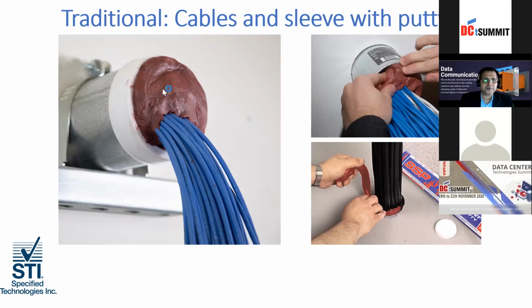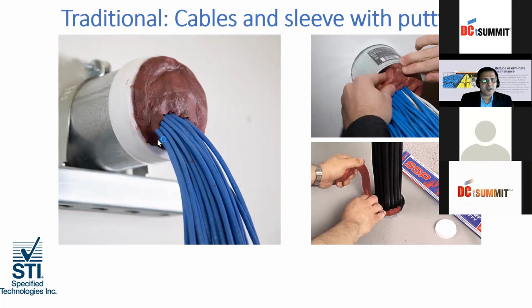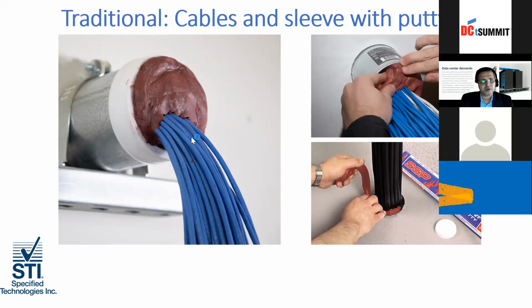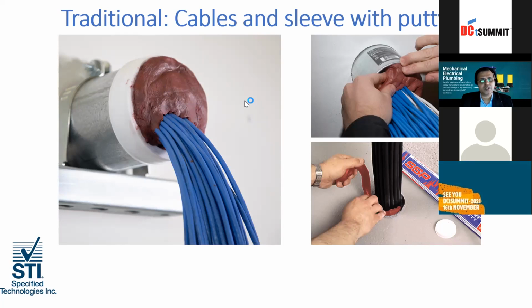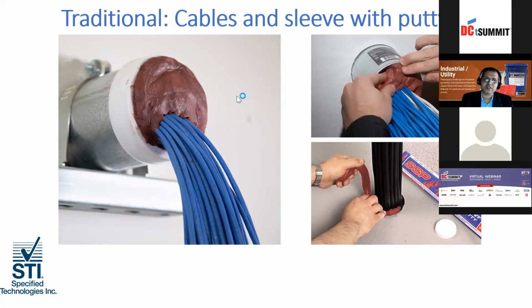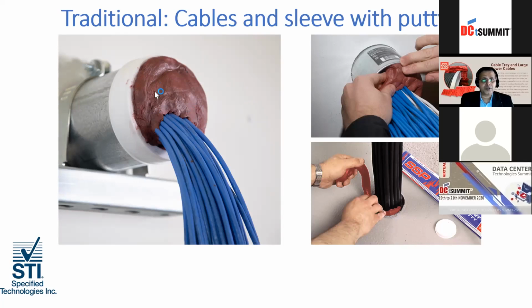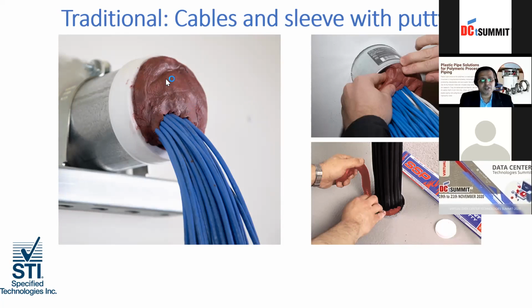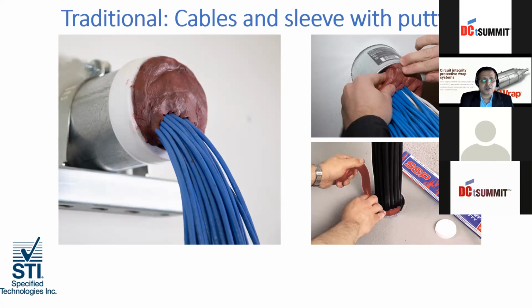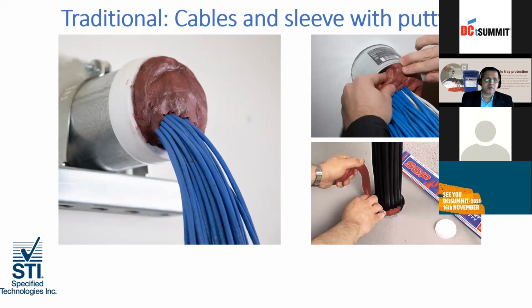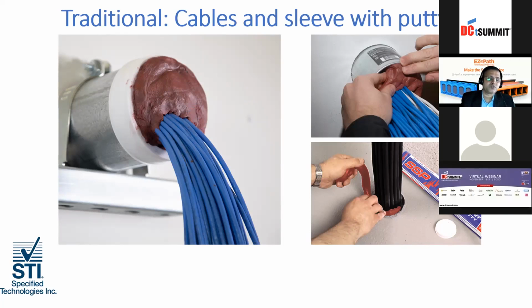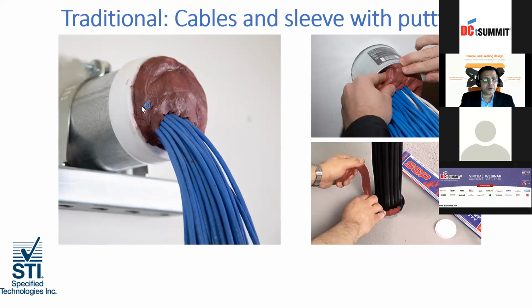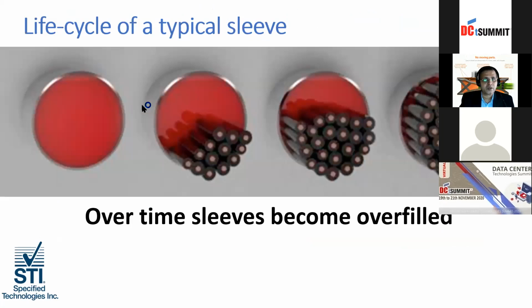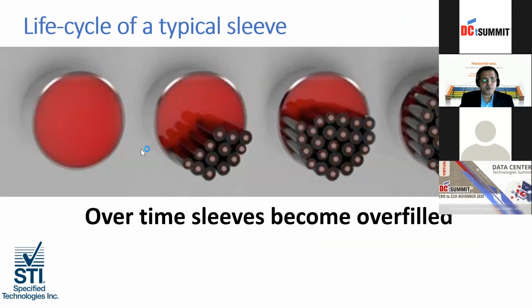Normally this is a metallic sleeve, and the cables pass through the sleeve, and the putty is installed properly. This is the ideal way. This is the correct one, because if the cables were more, the application would have failed, because the expansion of putty is 10 to 15 times. But if the amount of cables is more, it will surely fail. There's no UL system which shows that 100% fill will be supported with the same amount of putty. So here it's an overfilled scenario.